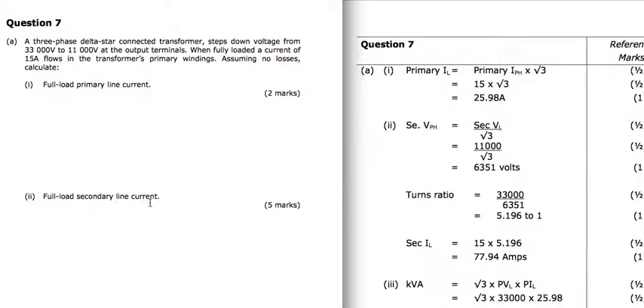Full load secondary line current, we're going to find the secondary phase voltage first. So the secondary phase voltage is going to be the line voltage, which is our 11 kV up here, divided by √3, and that will tell us the voltage across each of the phases in star. We've got a turns ratio of 33,000 to 6,351. So the turns ratio is all about the phase voltages. So there's our 33 kV of our delta, because the line and the phase are exactly the same, divided by our 6351 that we just calculated there, gives us 5.196 to 1. So that's the ratio between the windings and the voltages.